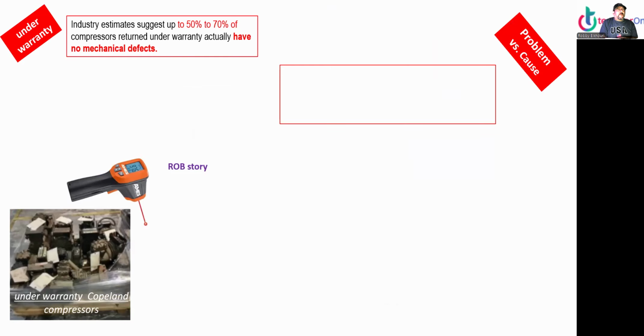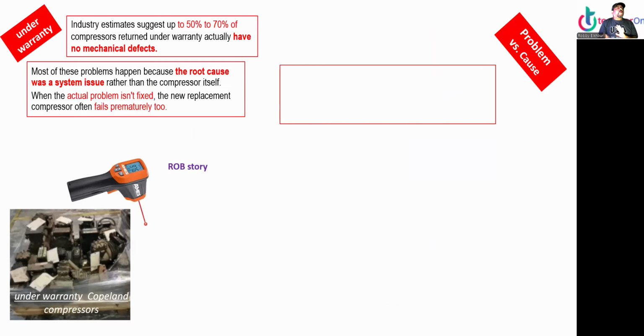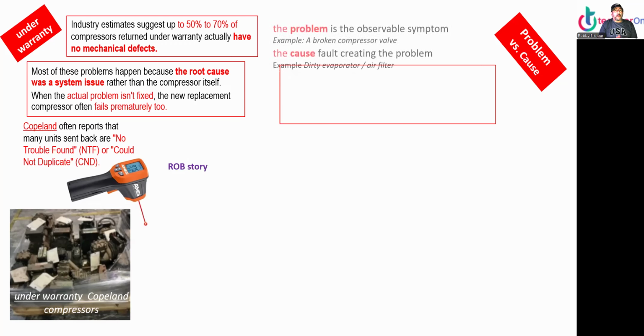They estimate 50 to 70% of compressors under warranty have nothing wrong with them. So most of these problems are because of the root cause of the system issue, rather than the compressor itself. When the actual problem isn't fixed, the new replacement will fail. Copeland often reports that many units sent back are no trouble found or could not duplicate a fault.